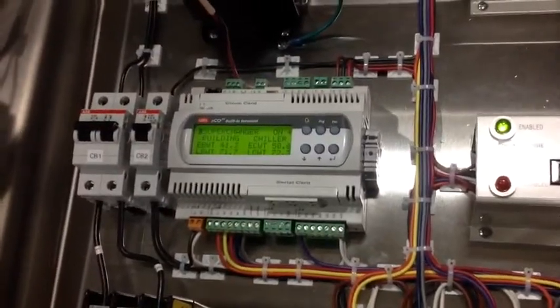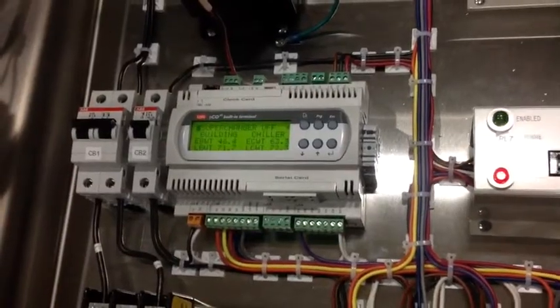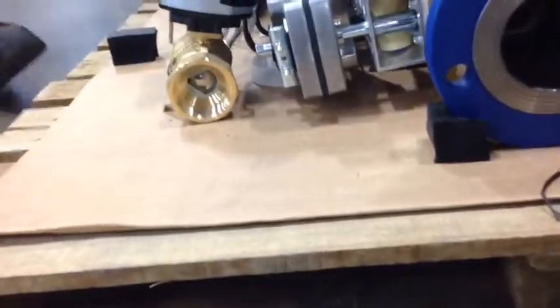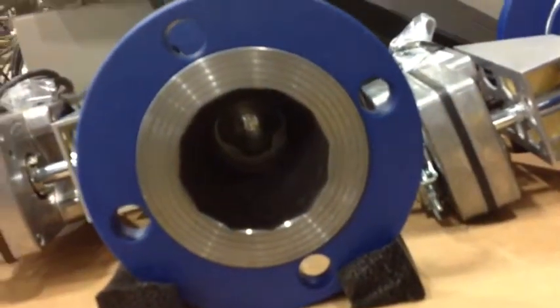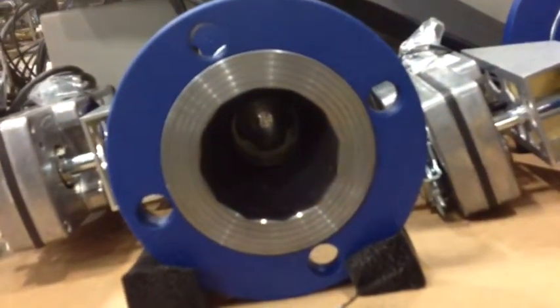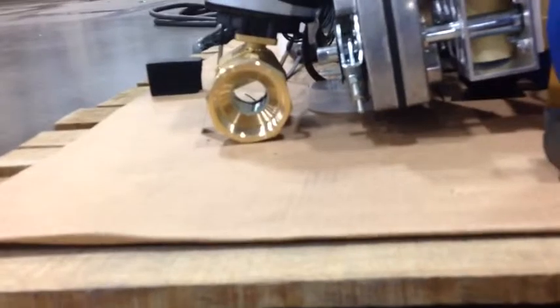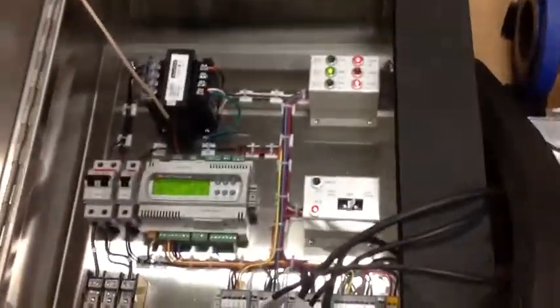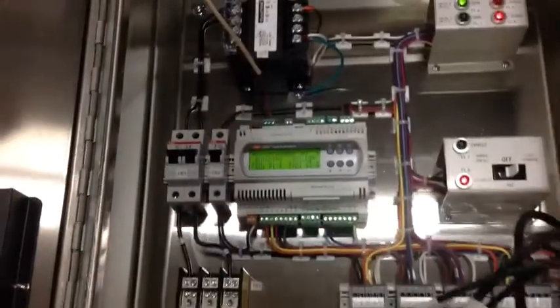And so when the water is cold enough from the comfort loop, we allow water to pass into the heat exchanger, and now the water's climbing into the 40s, into the 50s, and now we spin around to see that the bypass valve is stroking open. The isolation valves here are stroking closed, so they're already closed. Fairly quick acting actuator. And now we slide back, you can see that the bypass valve has now opened. So the bypass is short-circuiting water back to the comfort cooling loop, and then you can see that the indicator lights have flipped. The bypass valve open in green, and the 2 red lights up there indicate closed.